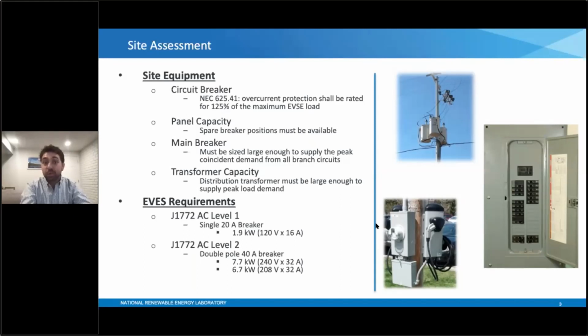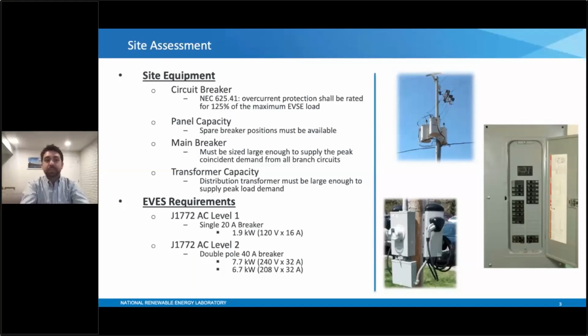In terms of their requirements for the previous section that we covered, the single 20 amp breaker is a common requirement for an AC level 1 unit. And that's primarily because they typically supply about 1.9 kilowatts to the vehicle at 120 volts. So that's a standard single leg of the 120 volt service coming into a home or even a facility. And they sort of require 16 amps. So as I mentioned before, you need that 125% buffer there. 16 amps times 1.25 gets you that 20 amp breaker. And it only needs a single breaker position because you're only pulling one leg of that 120 volt service.